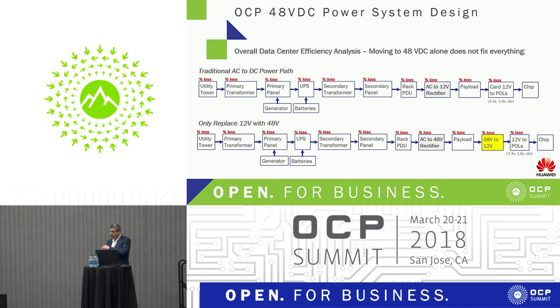That's the line on top. You got a generator, you got a UPS, you got batteries, secondary transformers, secondary panels, PDUs, AC to 12 volt rectifier in the current design, then you got your payloads, and on the cards you're converting your 12 volt down to your actual chip level voltages, 3.3, 1.8, whatever it is, and then the chip finally gets its power.